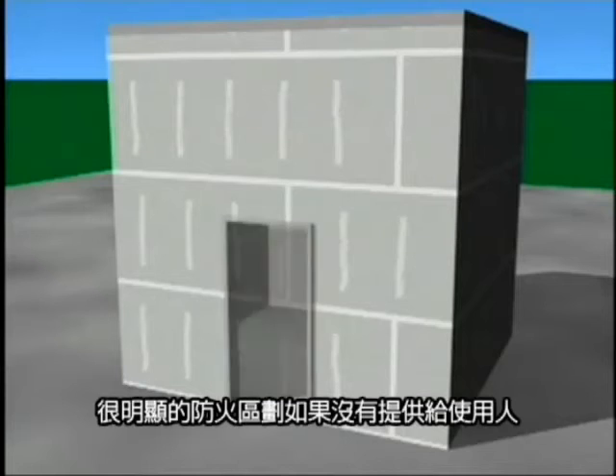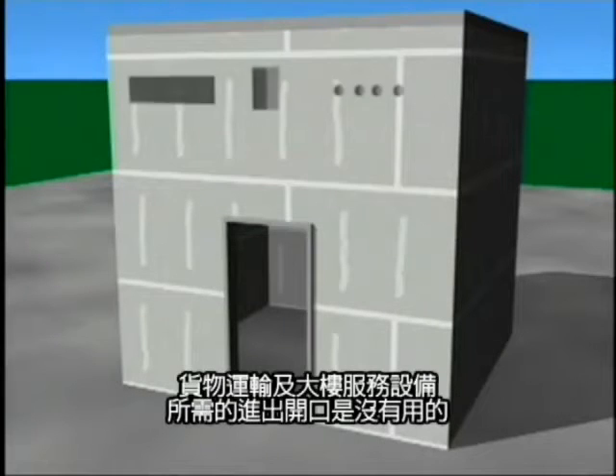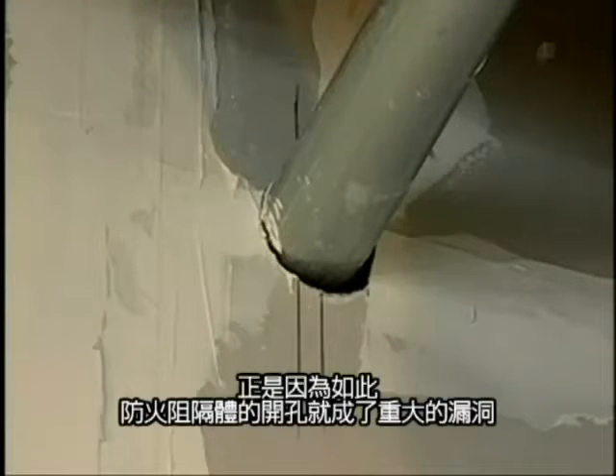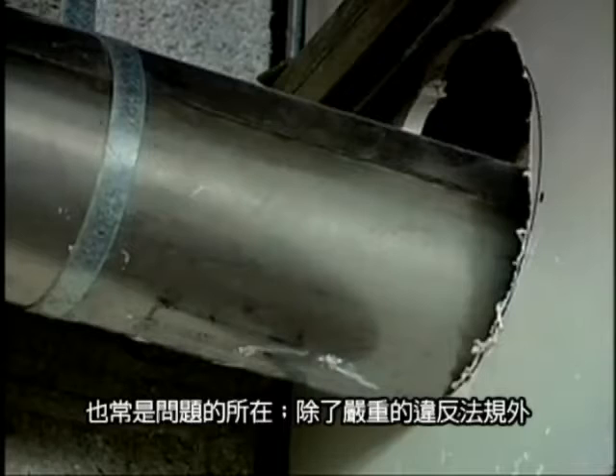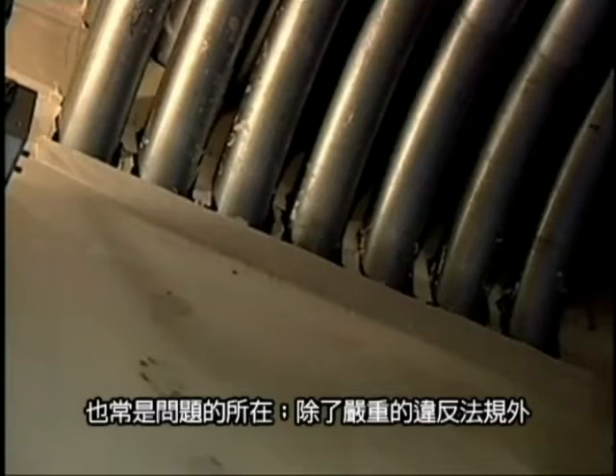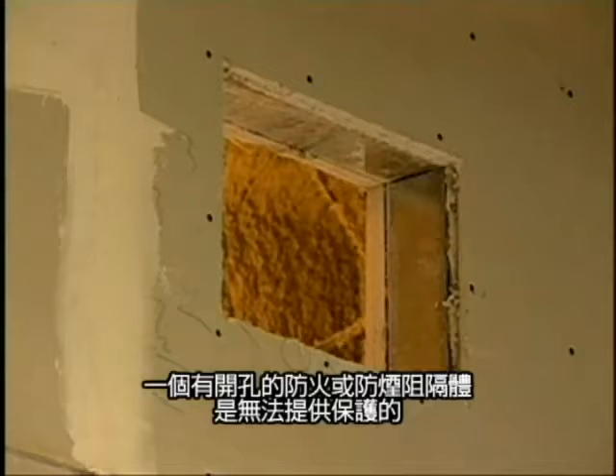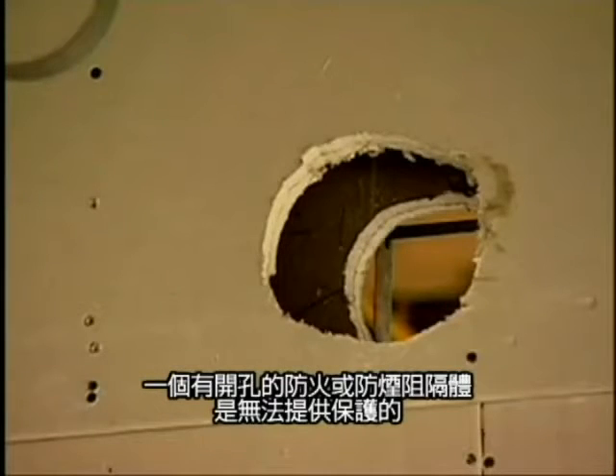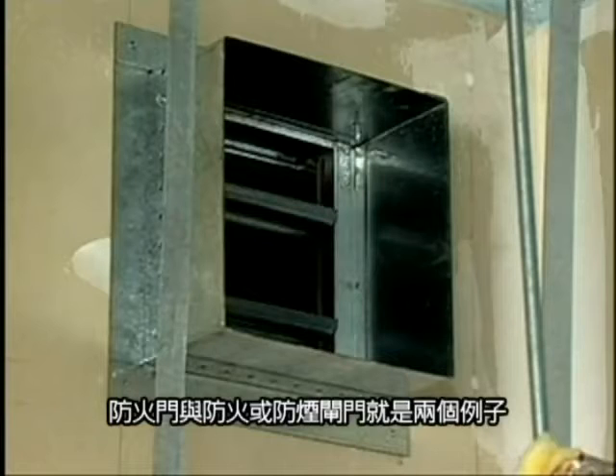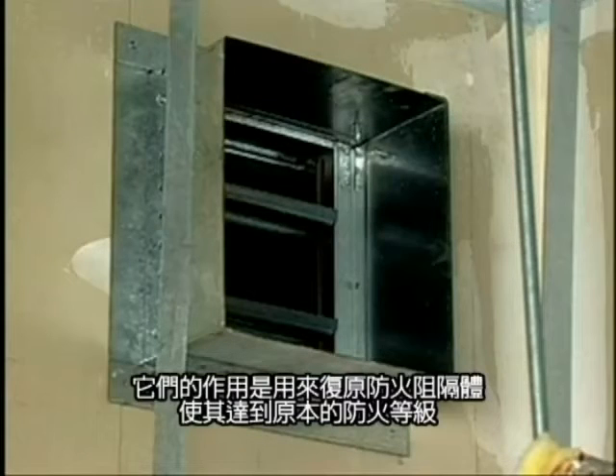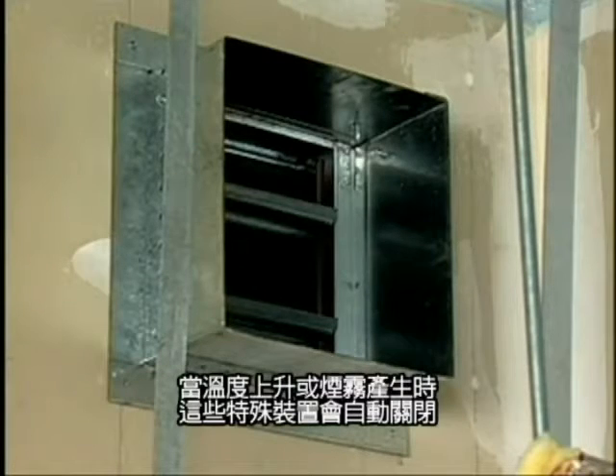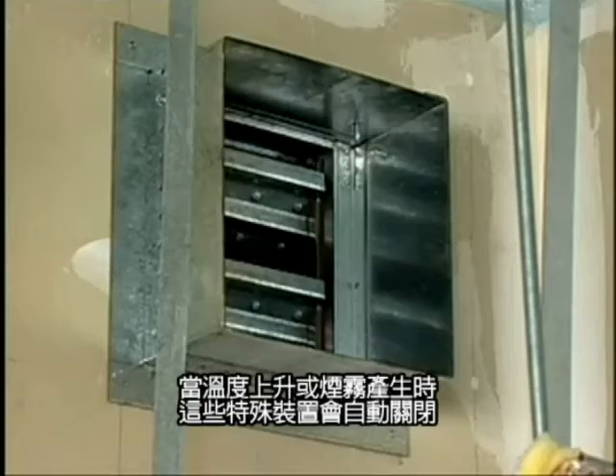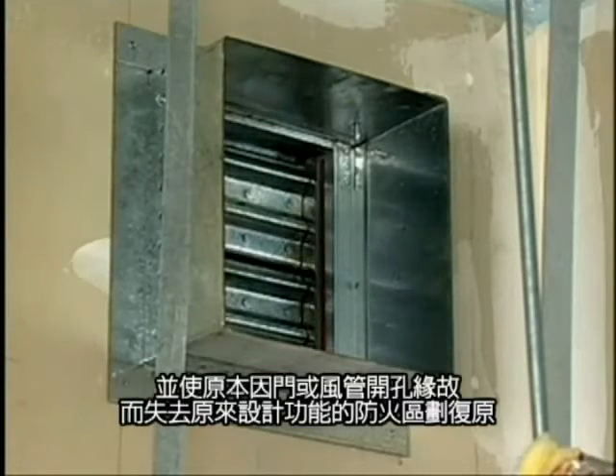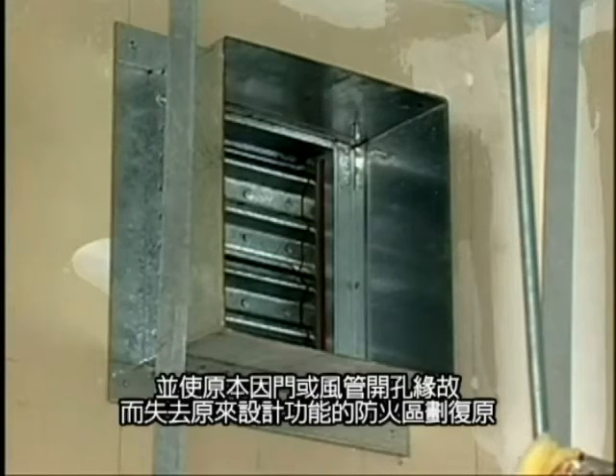Obviously, a fire compartment would be useless without openings to permit access for occupants, freight, and building services. For this reason, openings and barriers are a necessary evil, which presents a real problem. Besides being a very serious code violation, a smoke or fire barrier with a hole in it offers no protection. Fire doors and smoke or fire dampers are two examples of devices designed to restore a barrier to its original rating. These specialized devices will close automatically in the presence of smoke and/or elevated temperatures and restore the compartmentation that was lost because of a door or duct opening.